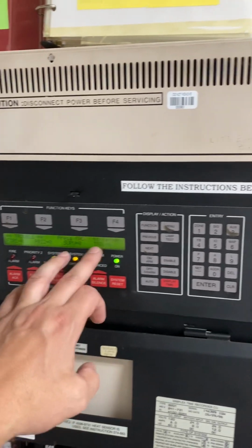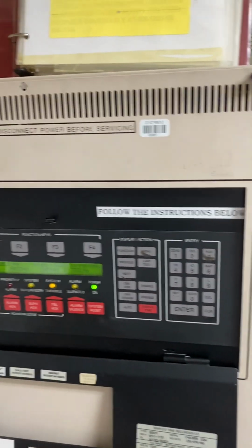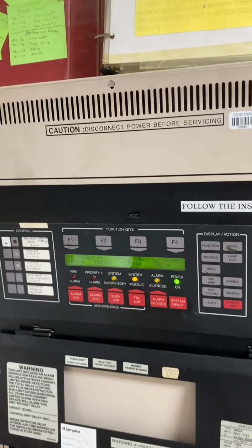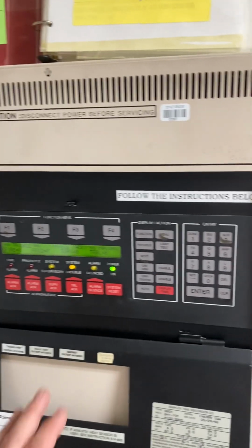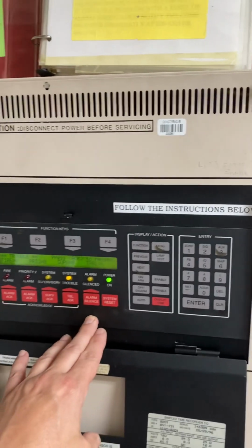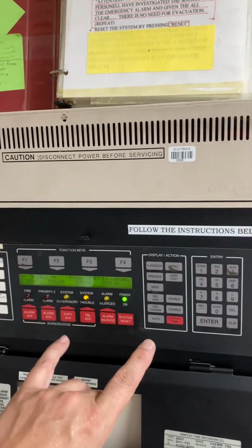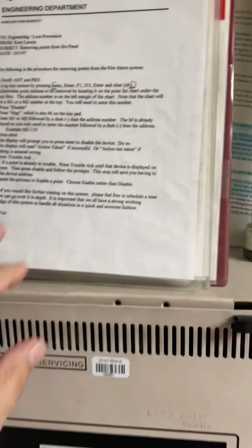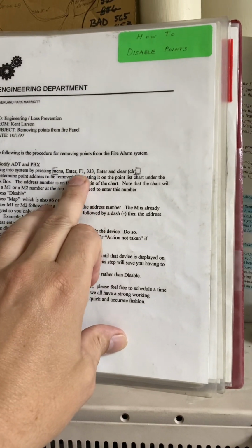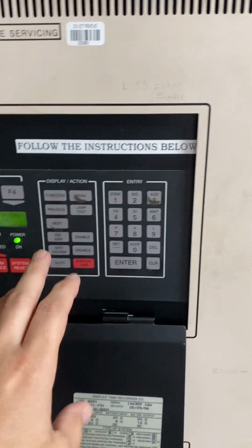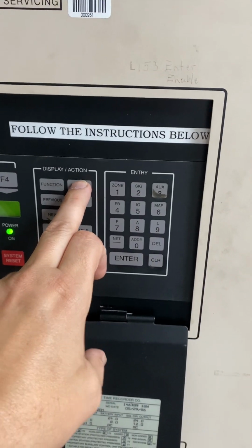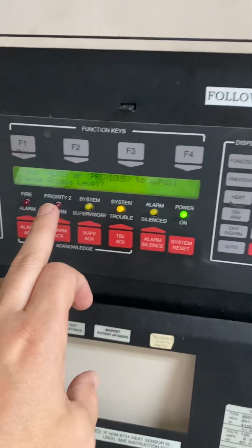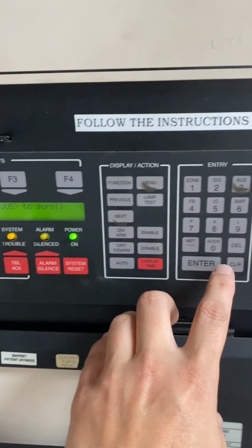Sometimes it's a bad device in the system, and if we try to reset, it will just glitch out again and the building will go back into alarm. So if that's the case, if it's a point that we need to disable that's being troublesome or problematic, it's when you go to the next page of the book, how to disable points. So it has the password in here and the sequence of buttons that you need to push, but I'll do it real quick here.